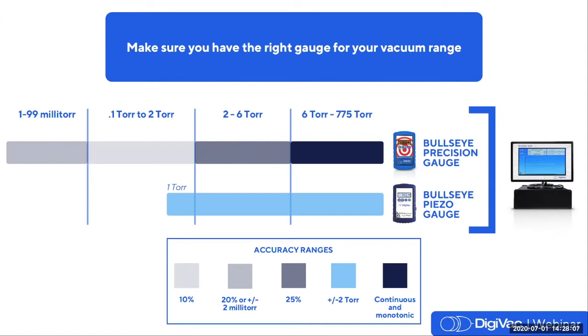If your gauge is not reading as expected, it's important to consider whether or not you have the right gauge for the range of vacuum that you're reading. Occasionally, we will have a customer that may buy a gauge believing it to be accurate in one particular range and find that it is really most useful in another. We have here displayed our bullseye precision gauge, which is a thermocouple type gauge, and our bullseye piezo gauge, which uses a piezo resistive type sensor. These gauges appear similar just from first look, but they actually read different ranges of vacuum with different accuracy.